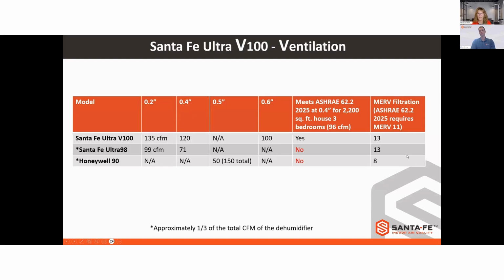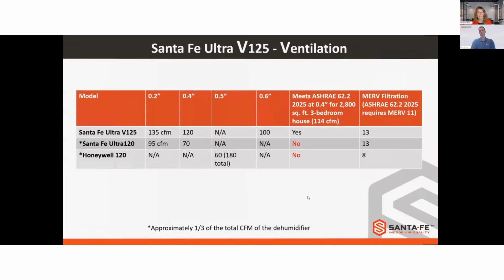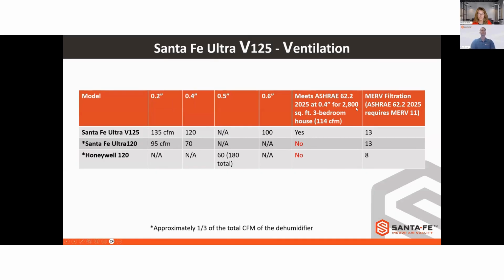And also, if you're not aware, the new ASHRAE 62.2 2025 requires MERV 11 filtration on all ventilation now. So obviously we have no problem meeting that with our units. And then if we look at the V125 going up to 2,800 square feet with a 3-bedroom home, we're going to need about 114 CFM of ventilation air. And again, we're struggling with our Ultras with the 6-inch ventilation duct in order to meet these increasing CFM ventilation rates for indoor air quality. So not a problem at all with this new V125.